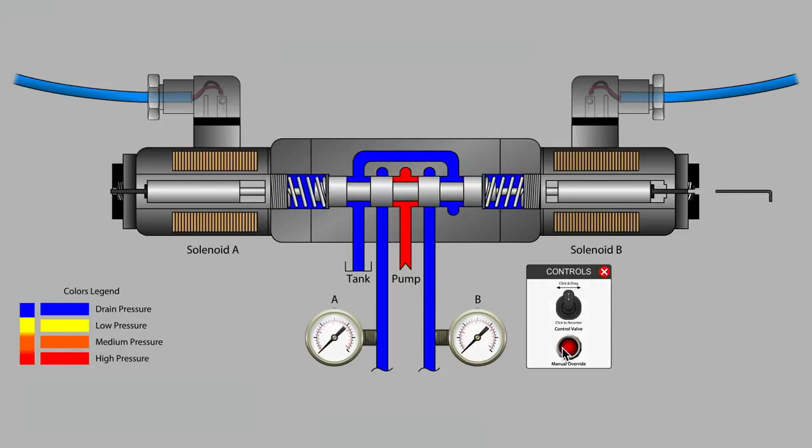Pushing on the mechanical override is a simple way to find out if the internal parts of the valve, namely the valve spool, is still free to move and operating normally.